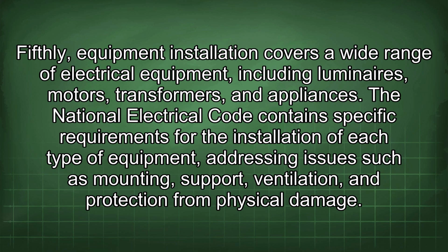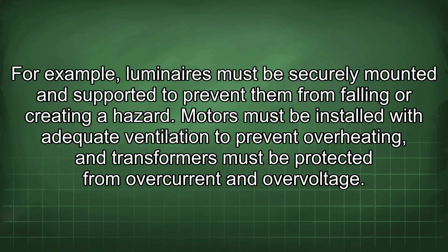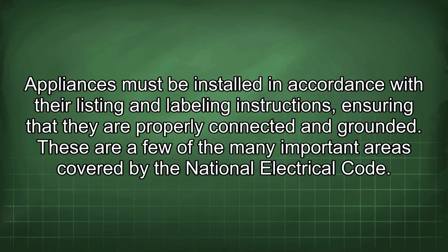Fifthly, equipment installation covers a wide range of electrical equipment, including luminaires, motors, transformers, and appliances. The National Electrical Code contains specific requirements for the installation of each type of equipment, addressing issues such as mounting, support, ventilation, and protection from physical damage. For example, luminaires must be securely mounted and supported to prevent them from falling or creating a hazard. Motors must be installed with adequate ventilation to prevent overheating, and transformers must be protected from overcurrent and overvoltage. Appliances must be installed in accordance with their listing and labeling instructions, ensuring that they are properly connected and grounded. These are a few of the many important areas covered by the National Electrical Code.